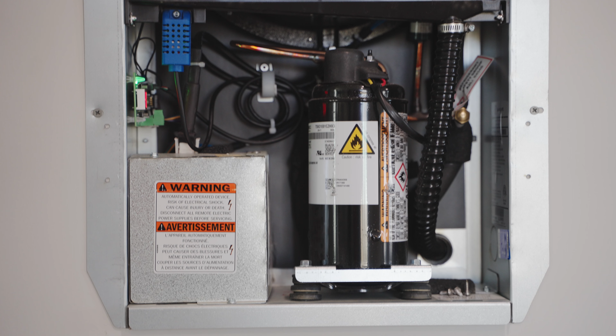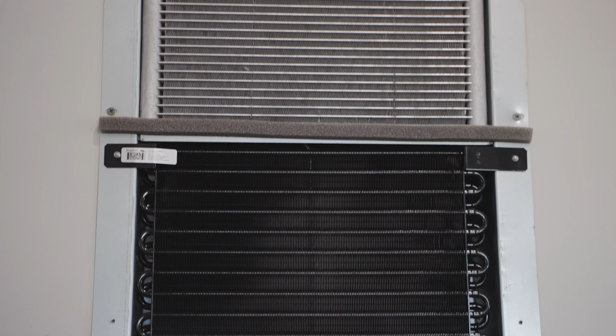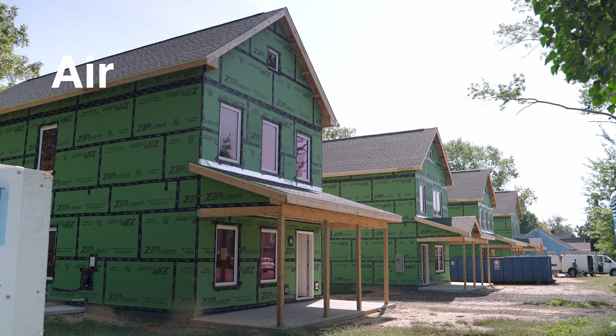One thing you'll find with a passive house is that it retains heat incredibly well, as it should. It also retains moisture that comes from just daily life. So to control that latent load, or the heat load associated with moisture, we've added supplemental dedicated dehumidification with an in-wall dehumidifier that will keep our interior relative humidity at no more than 55% all year round.